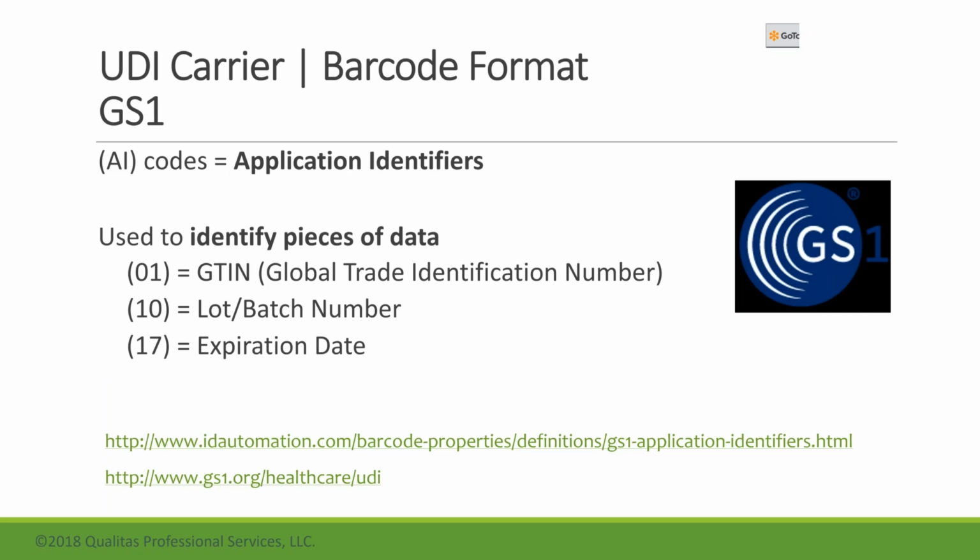agency that you choose to use for your UDI. The most popular one throughout the world is GS1, using their barcode formats. The other one is HIBC, and I'll just go into that briefly. And then there's ICCBBA for your blood and tissue donor. Not very much used because it's very specific to that industry.